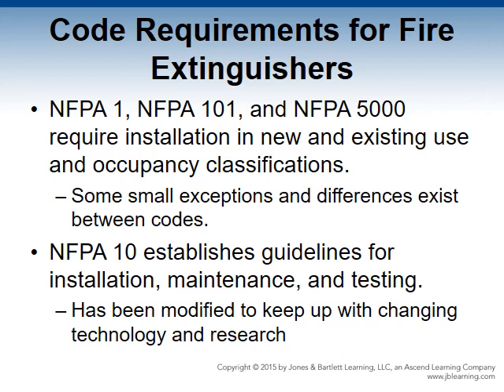There are differences between the codes and additional requirements and exceptions in each. NFPA 101 does not require fire extinguishers for new or existing educational occupancies, but NFPA 1 and NFPA 5000 do. Both NFPA 101 and 5000 do not require fire extinguishers in hotels or apartments when an approved and supervised automatic fire sprinkler system is installed throughout the building. NFPA 10 is a minimum guide for people who select, purchase, install, approve, list, design, and maintain portable extinguishing equipment. NFPA 10 was recognized as the standard in 1921, with over 36 editions since then to keep up with research, changing technology, and new suppression products.